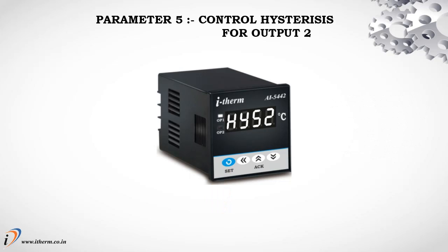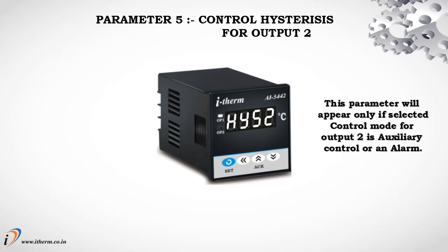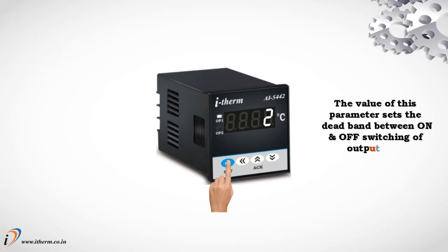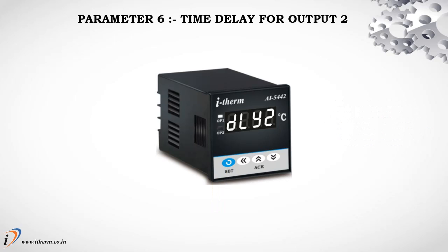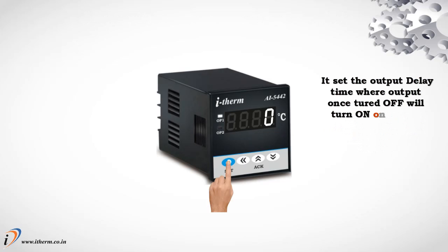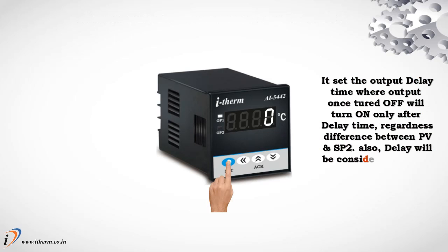Parameter 5. Control hysteresis for output 2. This parameter will appear only if selected control mode for output 2 is auxiliary control or an alarm. The value of this parameter sets the dead band between on and off switching of output load. Parameter 6. Time delay for output 2. This parameter will appear only if output 2 is configured as an auxiliary control output. It sets the output delay time where output once turned off will turn on only after delay time, regardless of difference between process value and setpoint 2. Also, delay will be considered at every power on.